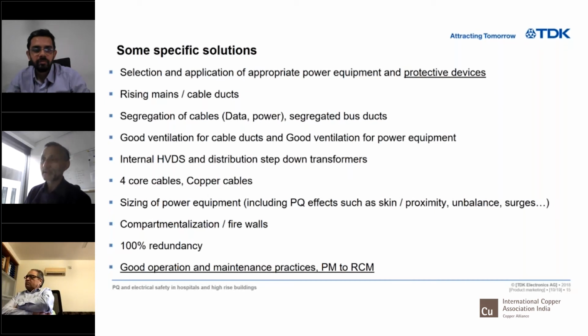Then we should have the right design of rising mains or cable ducts. Most important is the segregation of cables, data and power, and segregated bus ducts. So even in the case of a flashover, it's compartmentalized. The most important thing is good ventilation for cable ducts and good ventilation for power equipment. Like what Mr. Jain said, I have opened some of these cable ducts. You can see the heat. You can feel the heat hitting your face.